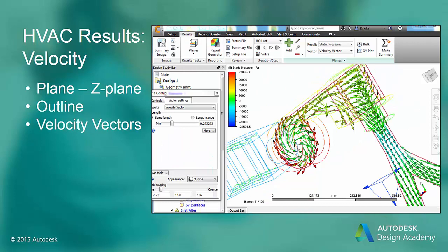We can look at the flow direction by plotting velocity vectors on cutting planes. A cutting plane normal to the Z direction is placed at the centerline of the blower. The vectors show the centrifugal flow pattern due to the blower rotation, and are colored by pressure, so again you see the pressure rise across the blower. When the flow reaches the cylindrical filter, it is deflected down and around the flow resistance region, and the vector colors also show the pressure drop across the filter.